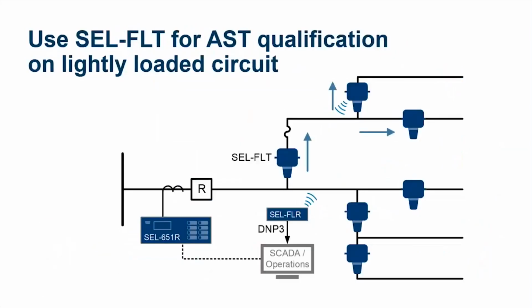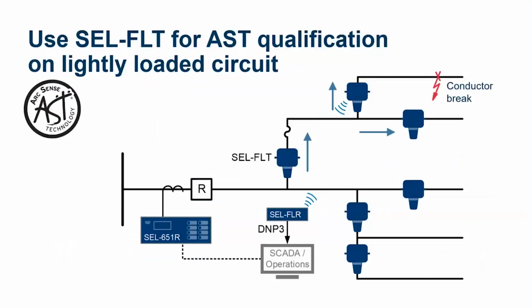In this case, let's say we have a fault on a relatively lightly loaded tap, and we have a conductor break. We still detect the high impedance fault with AST, although we don't have a significant amount of negative sequence current because it's very lightly loaded. However, we do detect a sudden loss of current on a single phase, and this goes back to our SCADA. Based on seeing a high impedance fault and one phase with a sudden loss of current, either our SCADA operator can make a decision, or we can have logic running in either my SCADA logic or in, say, an SEL real-time automation controller or something similar, to indicate that there's a trip and send a trip bit to the 651R in order to isolate that circuit.